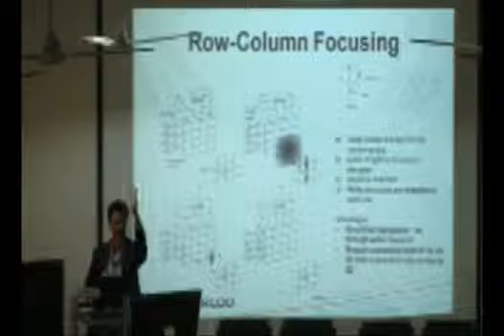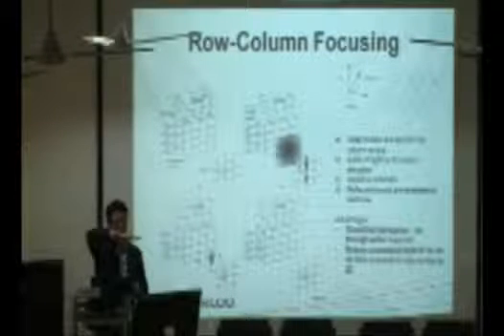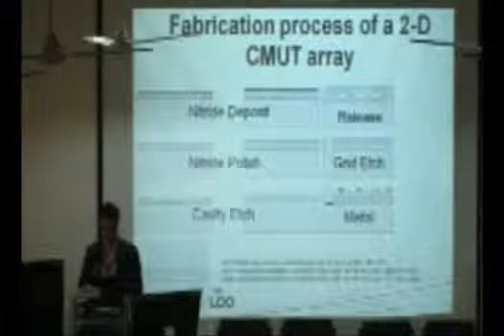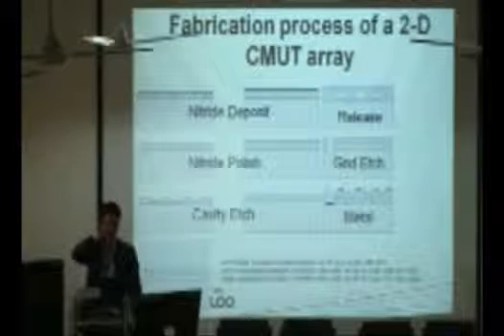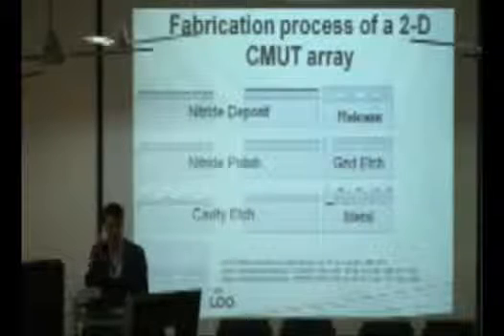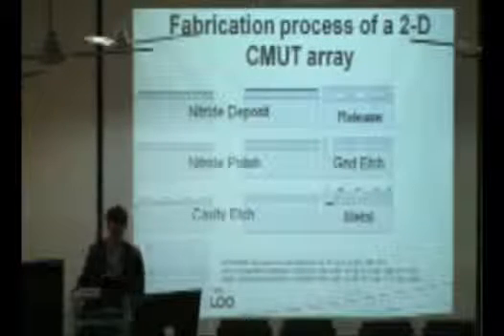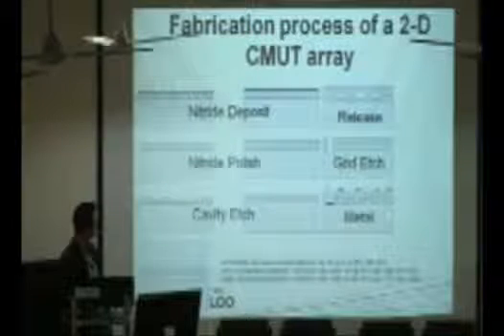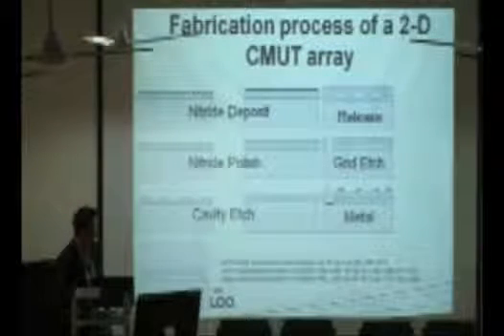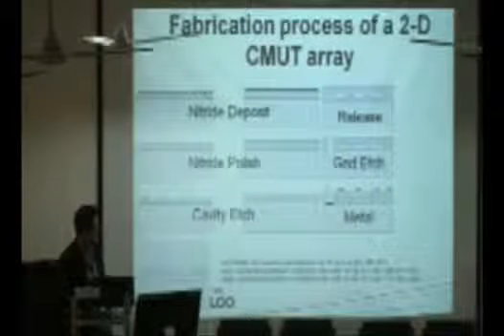So we are not firing each individual ultrasound element. We're firing from one column, and we're receiving by each row. We simplify the electronic processing of the ultrasound signal. And as it turns out, the quality of imaging for row-column is on par with that of addressing each individual element on a 2D array. I'm not going to talk about that, but if you're interested, I can provide you with our publication on this. This is a relatively simple MEMS fabrication technique of realizing the cavity as well as the top membrane, which is the drum membrane, and the top electrode to depress the membrane to generate ultrasound.